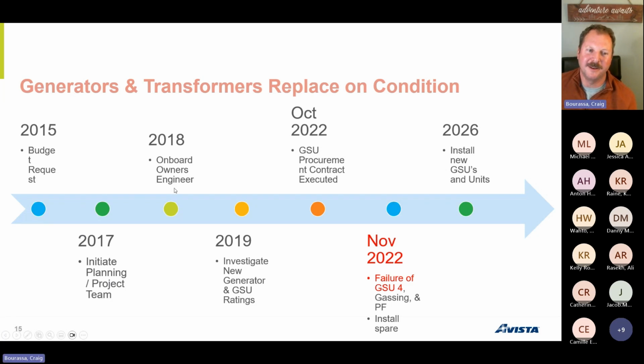In 2018, we hired an owner's engineer to investigate the project and determine the right transformers to put in. We looked at changing the voltage—these are really low voltage, like 4160 volts for the generator voltage. So we ended up changing the rating to about 6.9 kV. In 2019, we determined what size transformers to get.